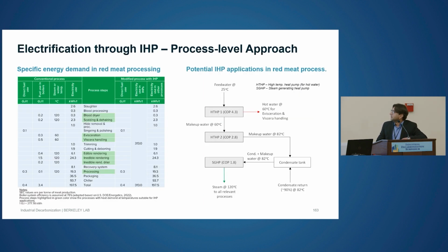Professor Kelly's colleagues. So instead of presenting the individual cases for all those 13 sectors, one example that I'm presenting today is red meat processing. In the table, you're seeing all the unit operations that are performed for red meat processing. The ones highlighted in green are the ones which are suitable for industrial heat pump applications because they require steam or hot water at temperatures that are suitable for industrial heat pumps. I'm not going into the details of the design, but we came up with a conservative general design to supply the heat that is needed for these particular processes.